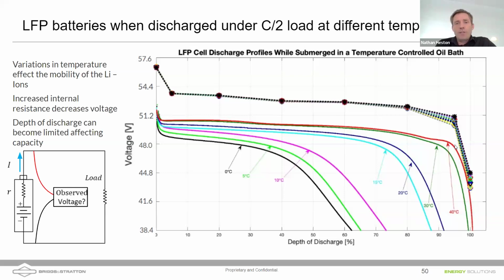At about 40 degrees Celsius, there's a drop at 50% state of charge, about that 1.2 volts we just mentioned. But if I get that battery really cold and try to discharge it at C/2, at 15 degrees Celsius, fairly cold, I'll see a slightly increased drop of another half a volt. But if I try this at 0 degrees Celsius, I can lose 4 or 5 volts on a 48-volt battery.